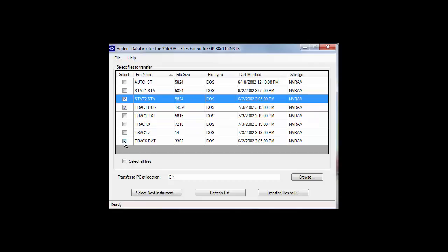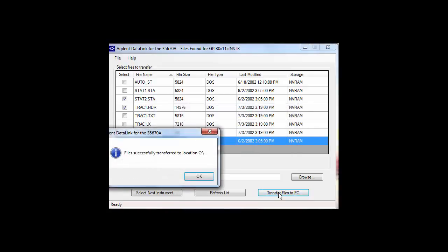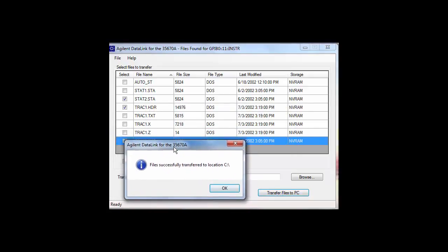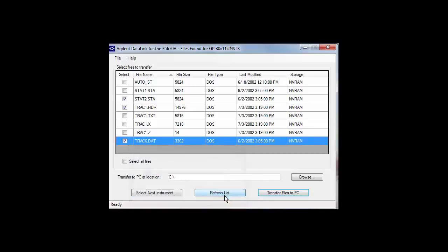The software will create three folders in the directory in which the files will be saved. One folder is called NVRAM for the files found in the non-volatile memory. One folder is called RAM for the files found in the RAM memory. And the third folder is called floppy for the files found on the floppy drive. Once the download is completed, you will see a message pop up stating files successfully transferred to the location you originally listed. In order to read the files most easily on the PC, we recommend saving them on the 35670A in a .txt format versus a .sdf format.